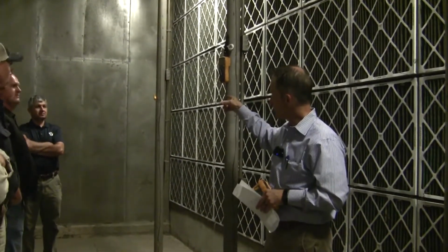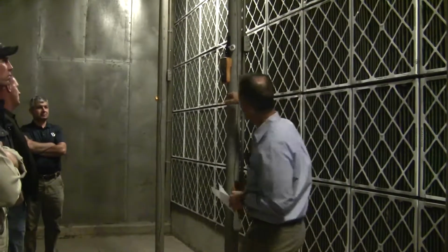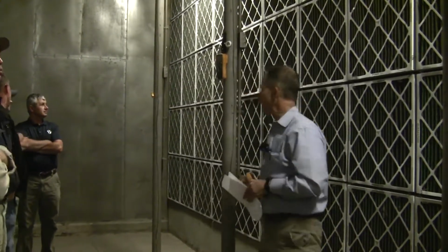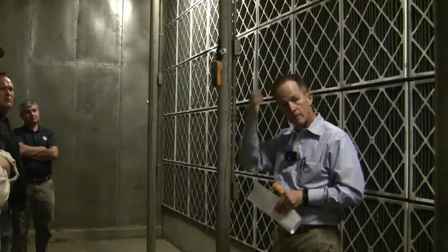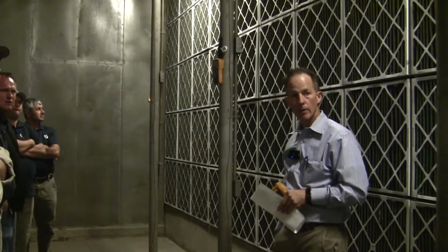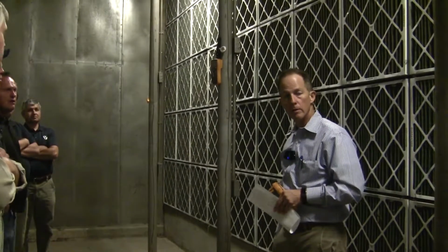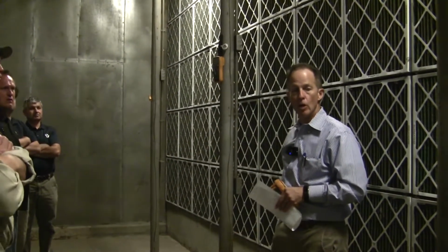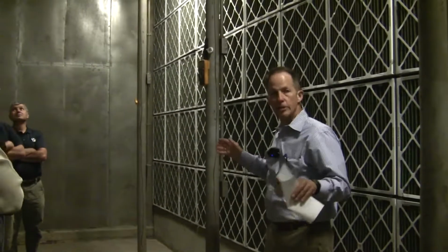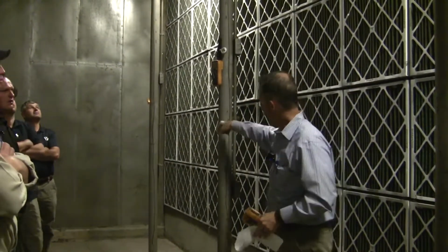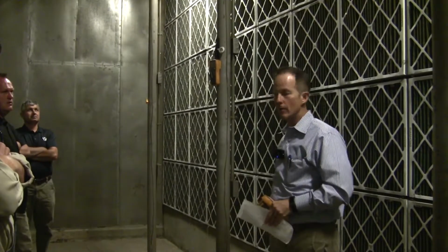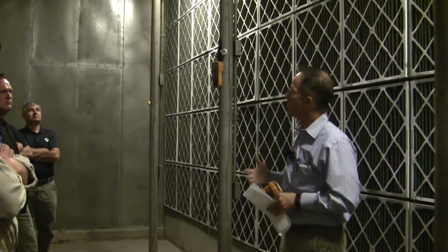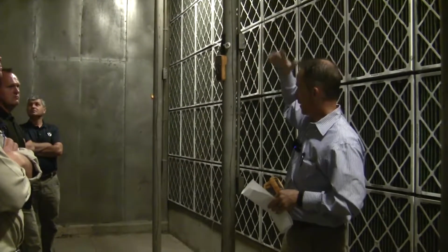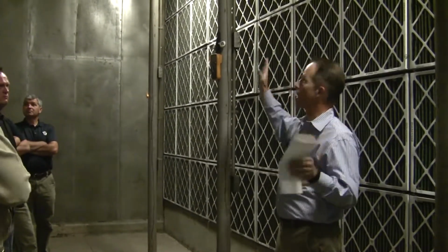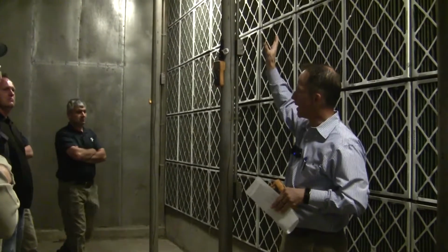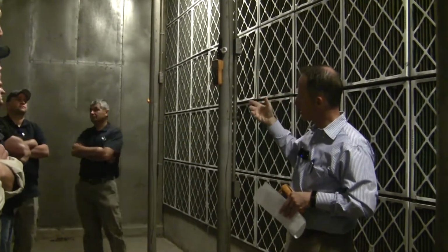What is yours? 73.7. It's going down though, so it'll take a second. The Fluke could be accurate to plus or minus 1 or 2 degrees, where the lollipop could be 3 to 4 degrees. Then there's another thing to consider: since I have 9 sensors in here, how accurate is one point? Because we're averaging, we should be pretty uniform right now since we shut the outside air, but we're still averaging, so it's something to take into consideration.